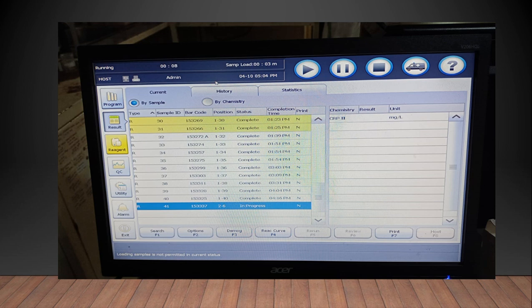It works in a very different way. The moment samples are picked, the instrument immediately gives you a sample stop, so you can keep loading. That doesn't happen with this particular instrument, because it has only one probe. So you need to give a pause. The moment you give the pause, the instrument tells you how much time it will take before you can give further tests. Once that is completed, it will tell you that the conditions for loading sample are satisfied. Now you can load the sample, and then give OK.